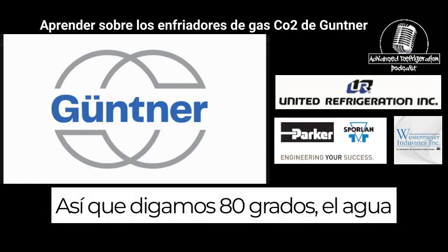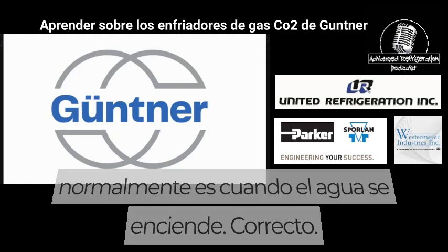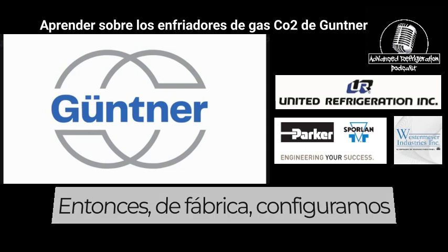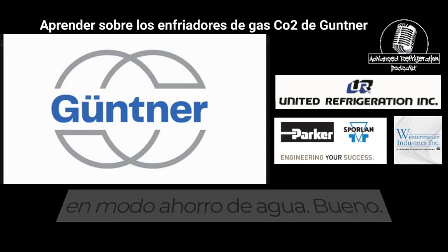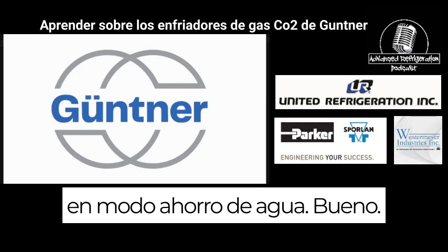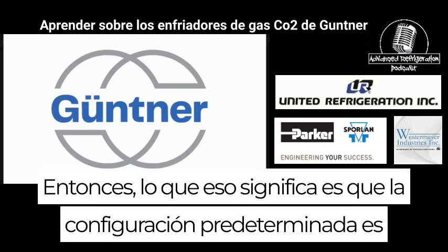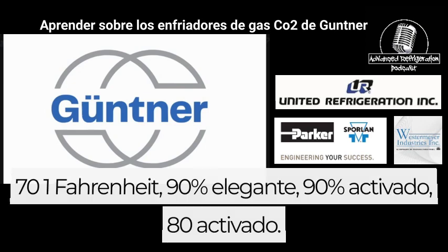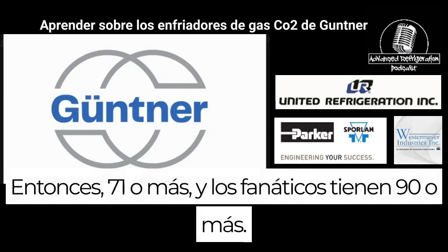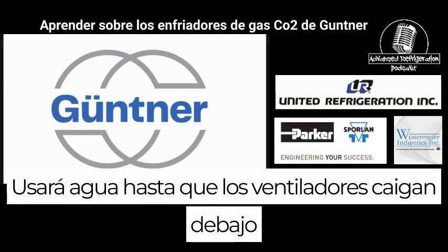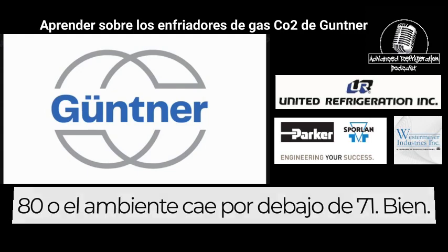So let's just say 80 degrees, the water, that's typically when the water comes on, correct? From the factory, yeah, we set it up in water savings mode. What that means is the default settings are 71 Fahrenheit, 90% fan speed, 90% on, 80 off. So at 71 or greater and the fans at 90 or more, it'll use water until the fans drop below 80 or the ambient drops below 71.